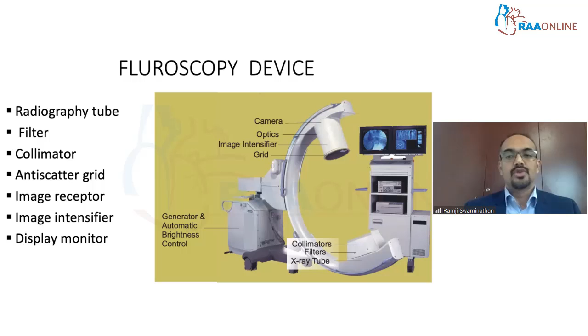So what are the parts of a fluoroscope? As you can see in the picture here, the X-ray generator is that part of the fluoroscope which generates the X-rays. Subsequently, the X-rays pass through an X-ray tube and then through a collimator. A collimator is nothing but something similar to a camera shutter. It controls the amount of X-rays that come out of the X-ray tube. As you can see here, this is the X-ray tube, and above that is the collimator. The X-ray tube generates and pushes out the X-rays, which ultimately pass through the collimator, which acts as a shutter for the X-rays, controlling the beam of X-rays which subsequently passes on to the patient.